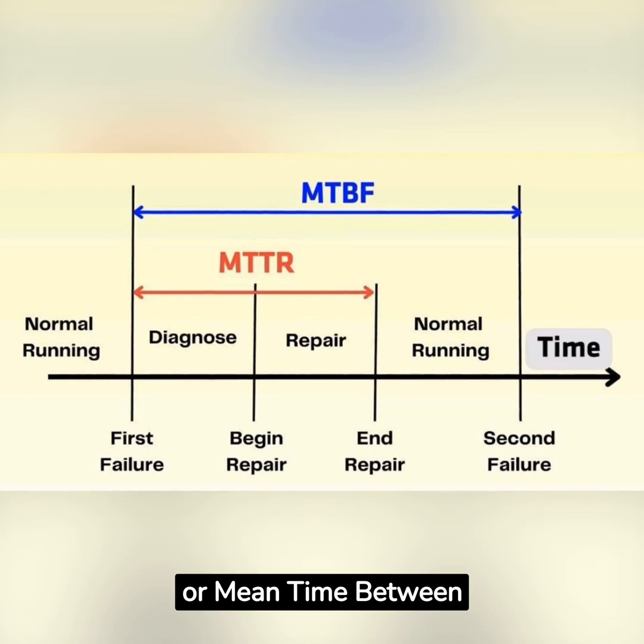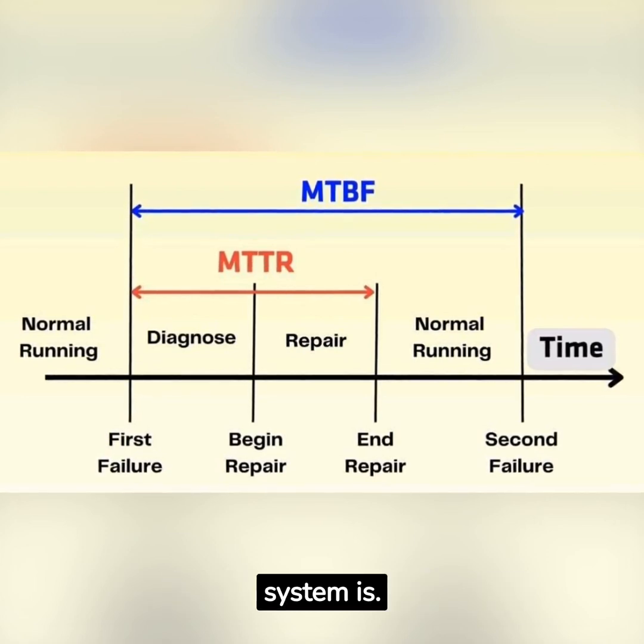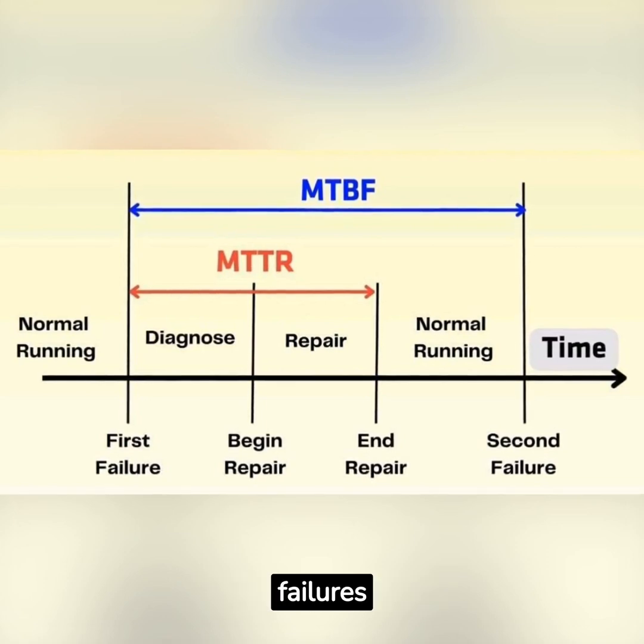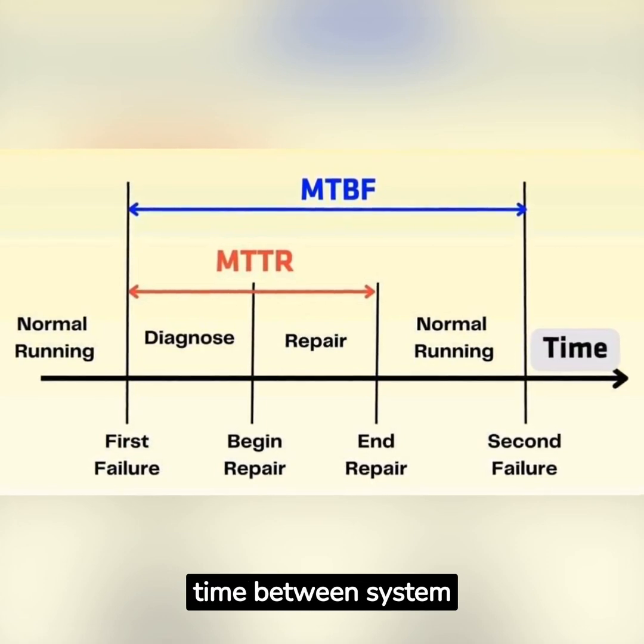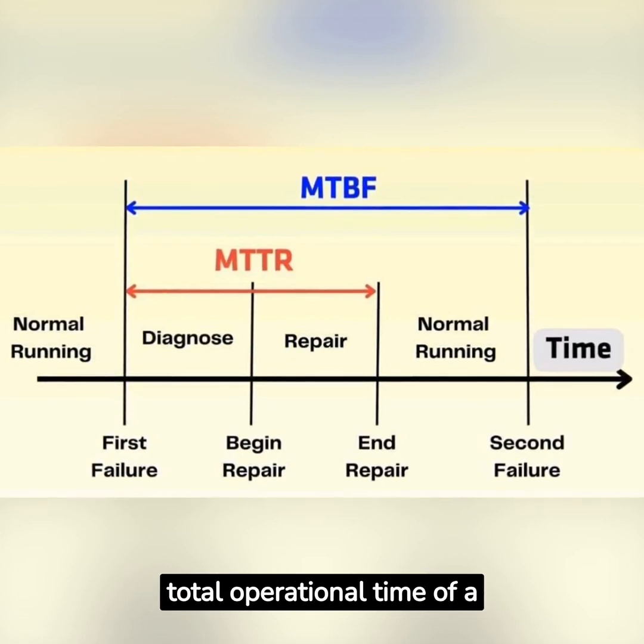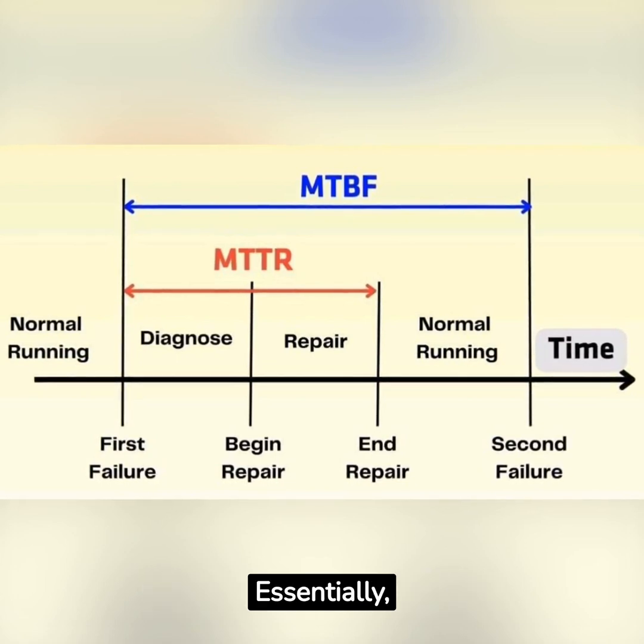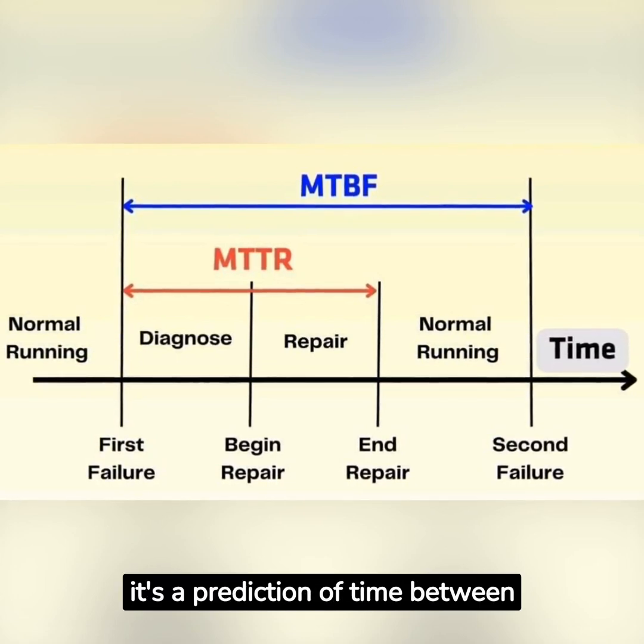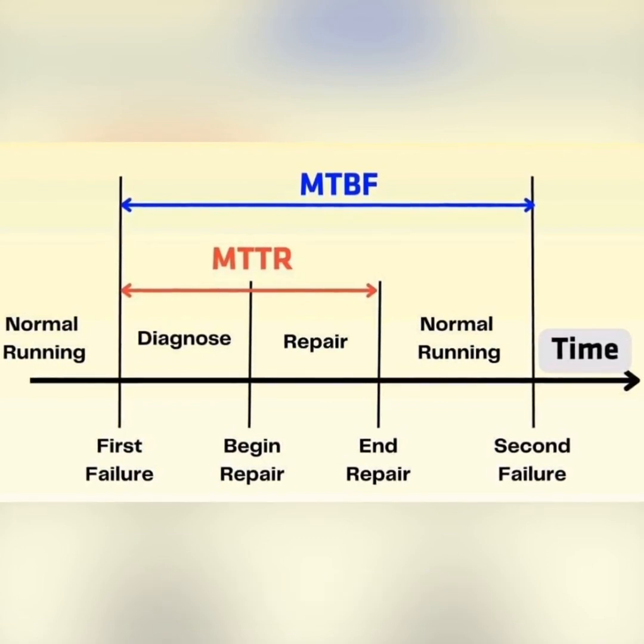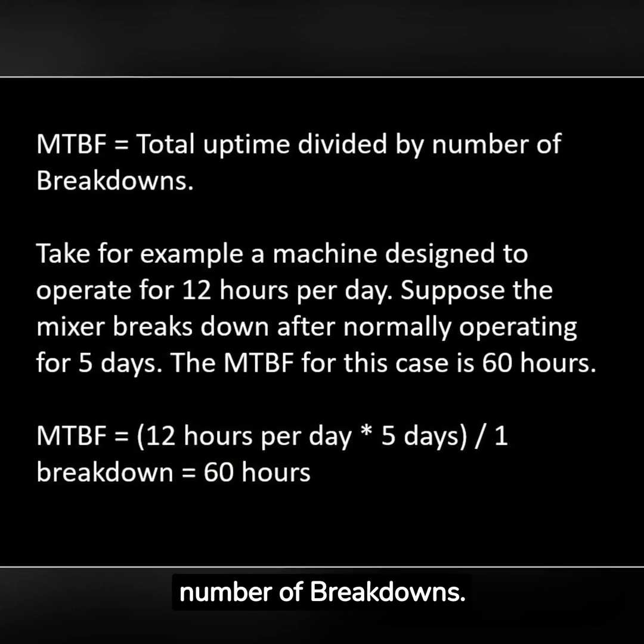MTBF, or mean time between failures, is a common measure of how reliable a product or system is. It is the average time between system breakdowns, calculated by adding up the total operational time of a system and dividing it by the number of failures. Essentially, it's a prediction of time between the inherent failures of a system during operation.